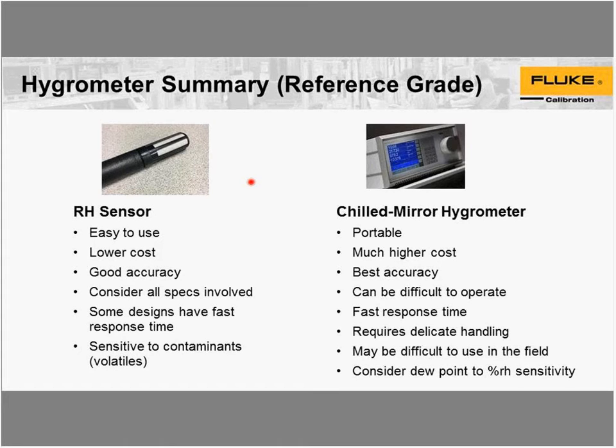So over here, this bullet with the RH sensor. Keep in mind these things are made out of a lot of different materials, and some of the materials, well, two things: different sensor technologies and designs, and then different materials involved in building them. Some of them can require a lot of soak time to fully realize their accuracy, or to fully stabilize and measure to their specifications.